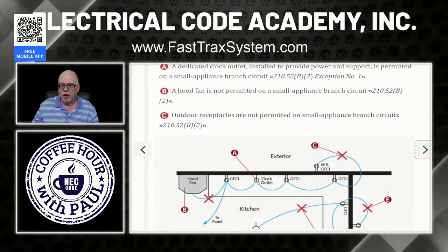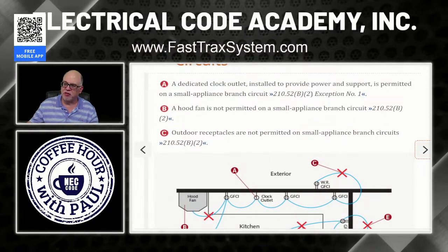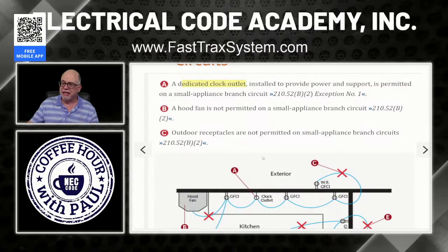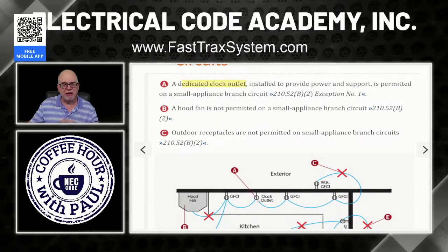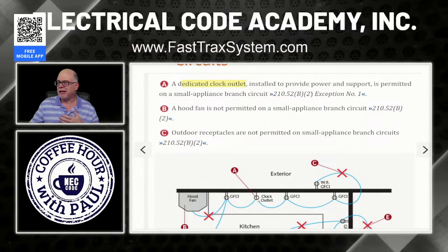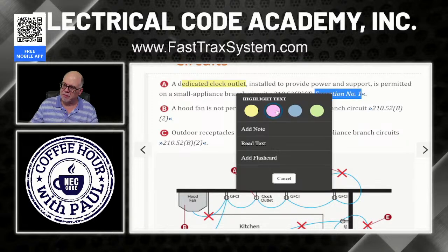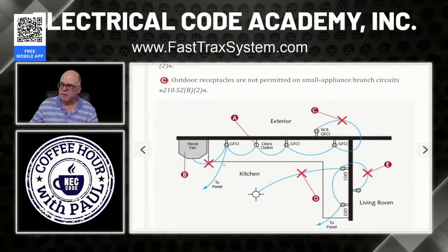Okay. Well, if that's the case, there is an exception to 210.52(B)(2) on what can be on these small appliance branch circuits. Well, I can have a dedicated clock outlet if I want. I don't see them anymore, but I could put that on there. It's not really going to pull anything. It has no real significance to the load, but that's okay under exception number one. That's not a problem.